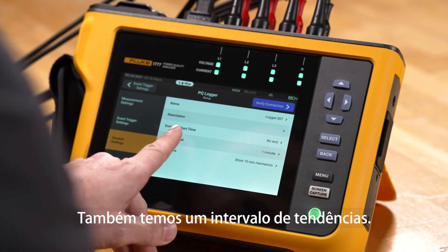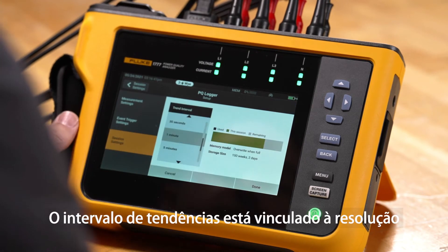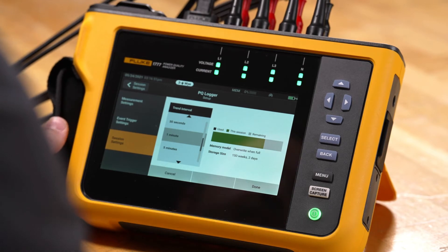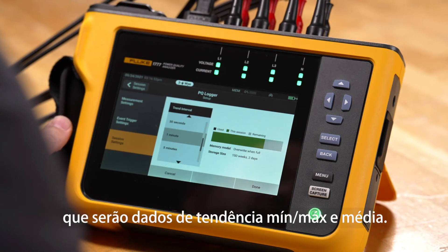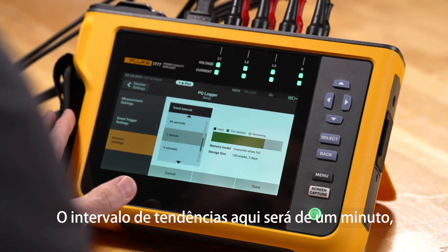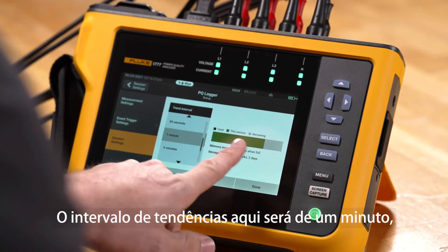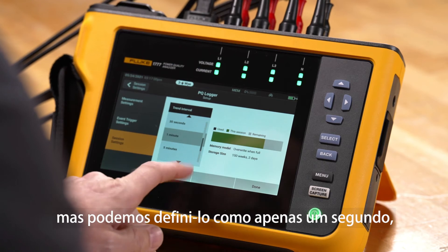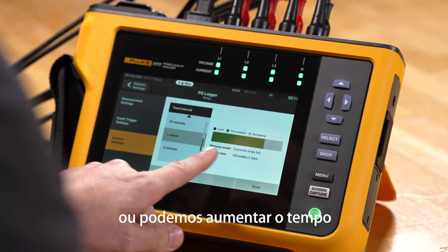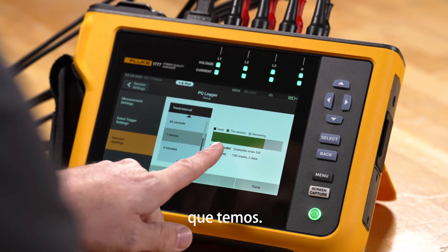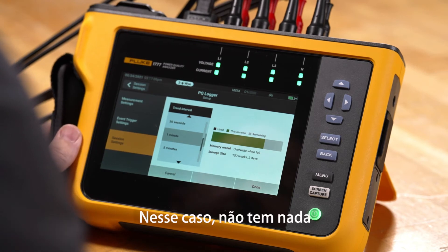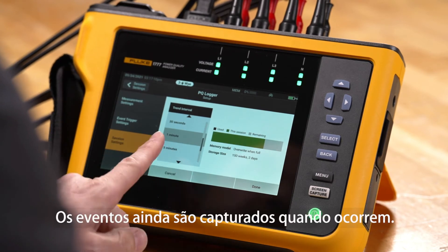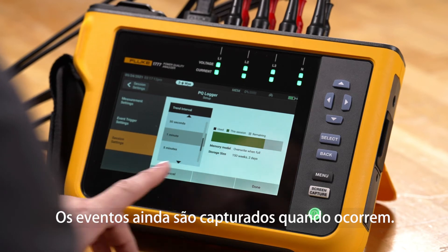We also have trend interval. Trend interval ties into the resolution of the trending data itself, which will be min, max, and average trend data. The trend interval here will be 1 minute, but we can set it for as low as 1 second or increase the time for a longer recording length. This doesn't have anything to do with your event capture — events are still captured when they happen.